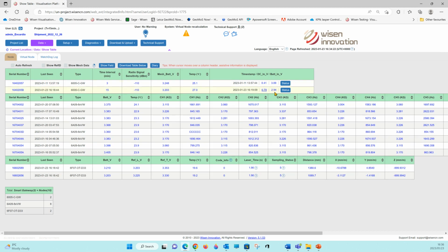And if we go back and we look at the other voltage, the 2.94, this is the D-cell batteries internally of the gateway. So in the first instance, if you've got a secondary incoming power, this voltage here is the backup, this is the UPS power, and this is the main power in the system. So something's incorrect here. You might want to share some details on what your DC in voltage is and how you've connected that up to the actual gateway itself.